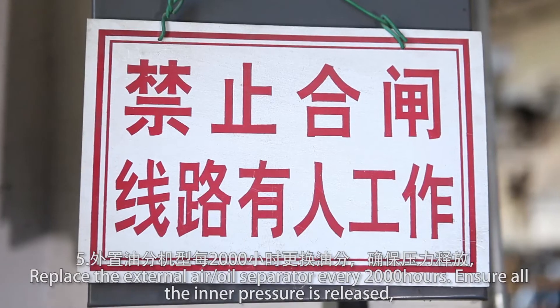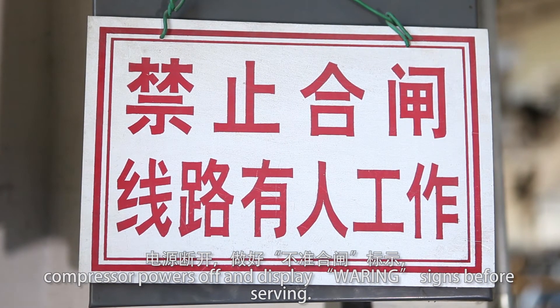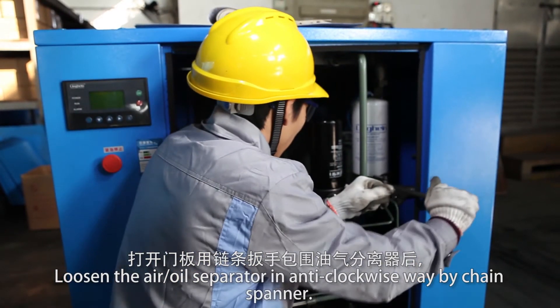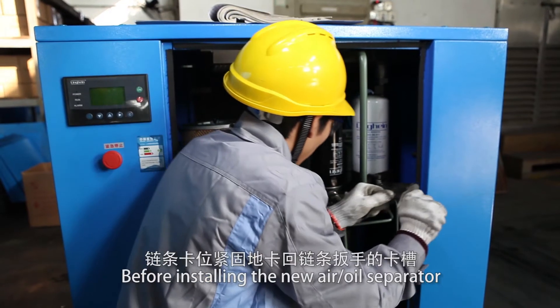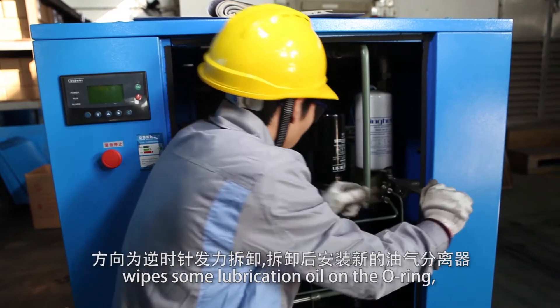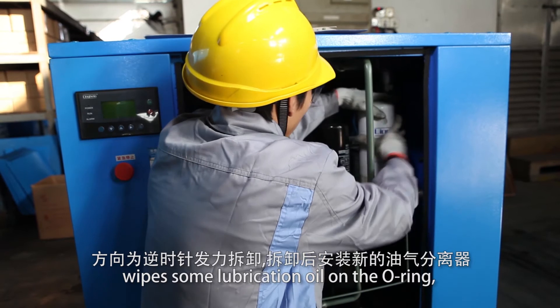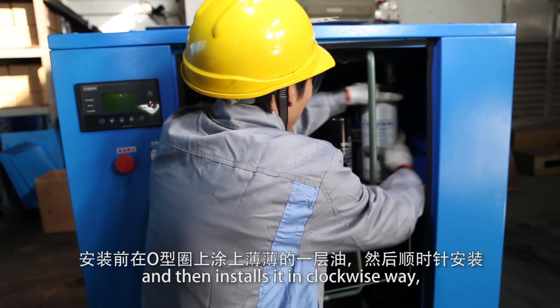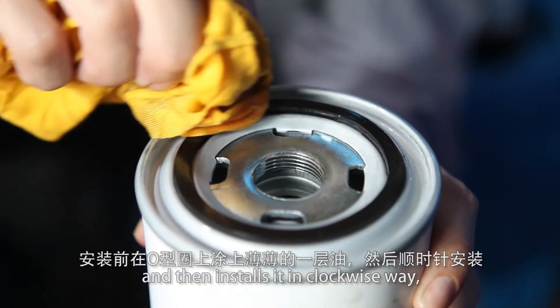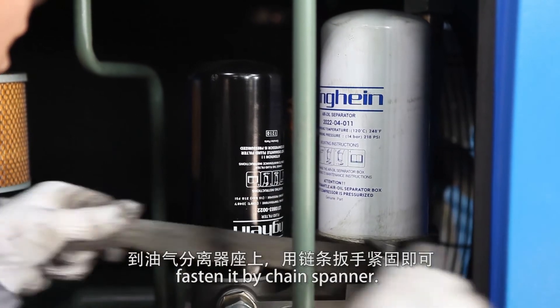Ensure all inner pressure is released and the compressor is powered off with a warning sign displayed before servicing. Remove the air-oil separator in an anti-clockwise direction using a chain spanner. Before installing the new air-oil separator, wipe some lubrication oil on the new O-ring. Install it in a clockwise direction and fasten it with the chain spanner.